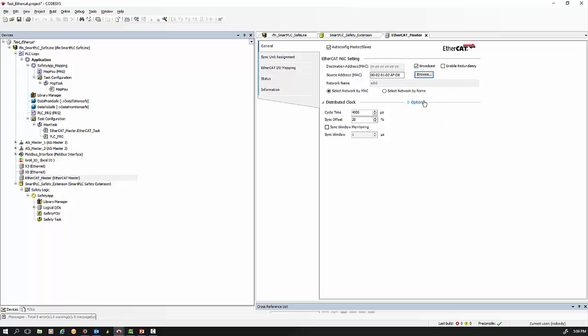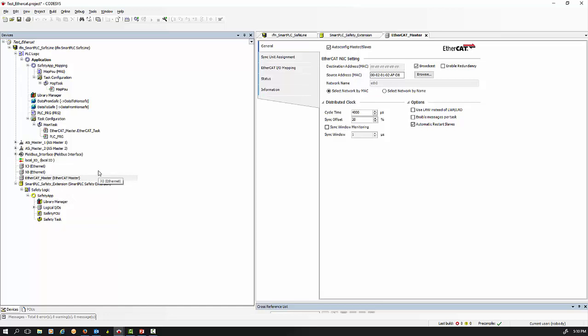A very important note: click on the settings and options and make sure you tick the box that says 'automatic restart slaves'. Otherwise, if you lose your EtherCAT comms due to network faults, it could be a problem re-establishing communication. That should do it for the EtherCAT master side.